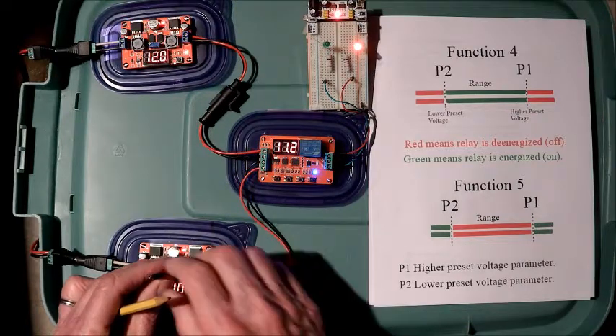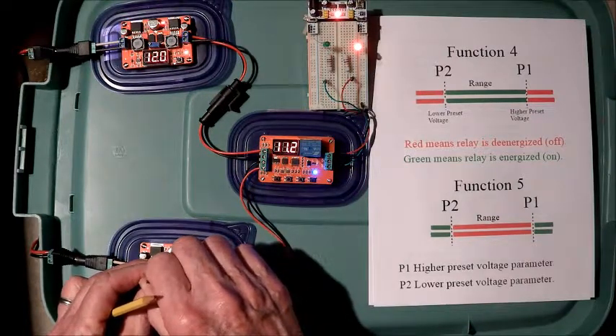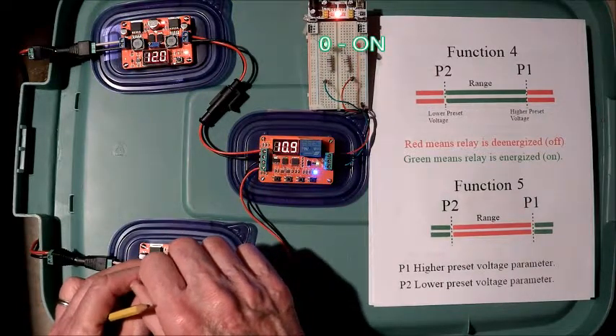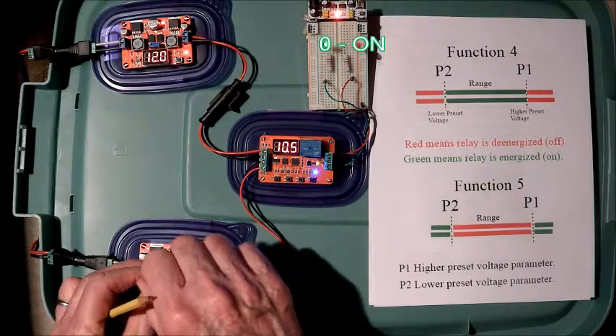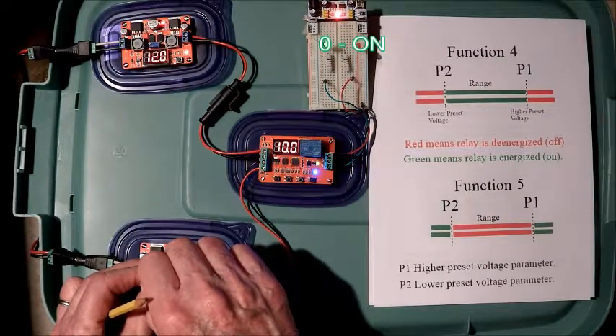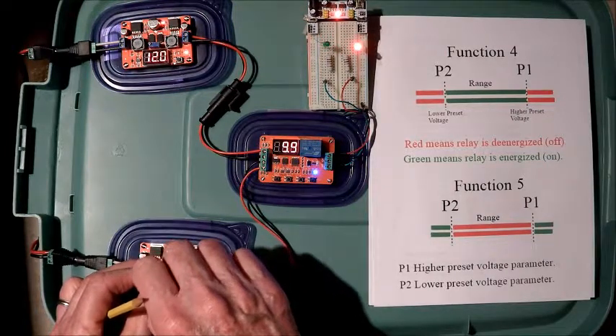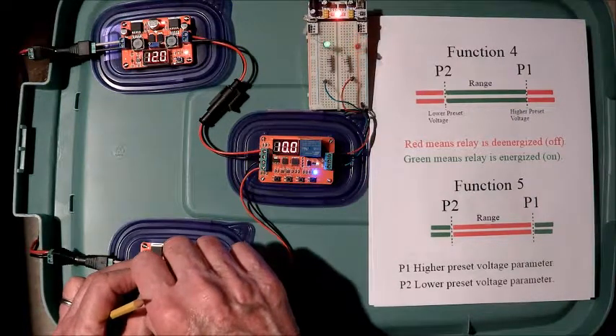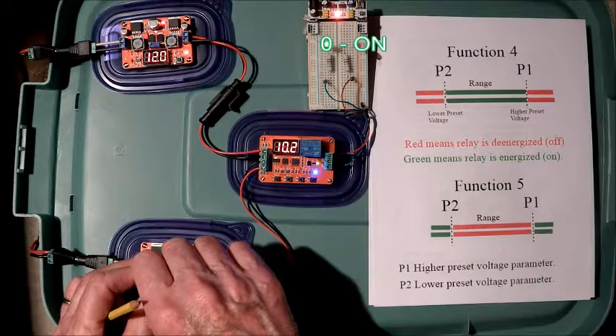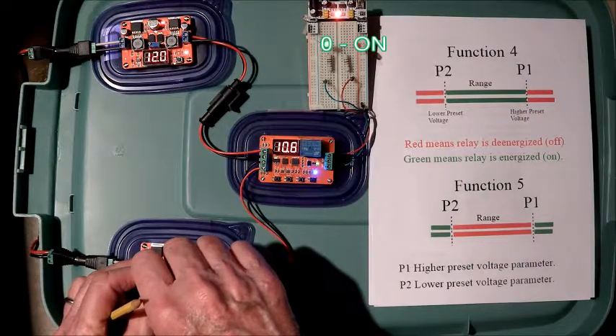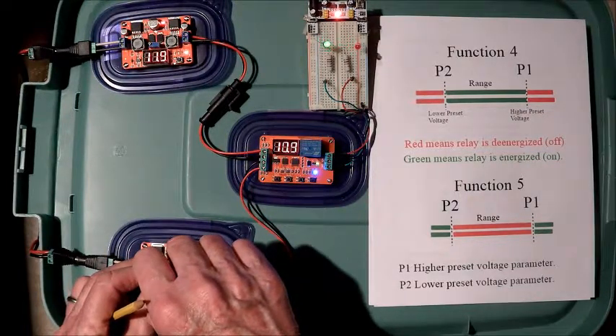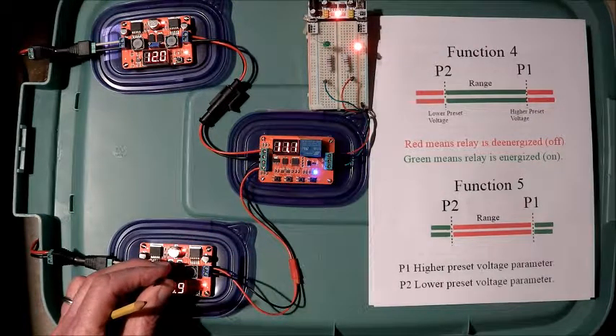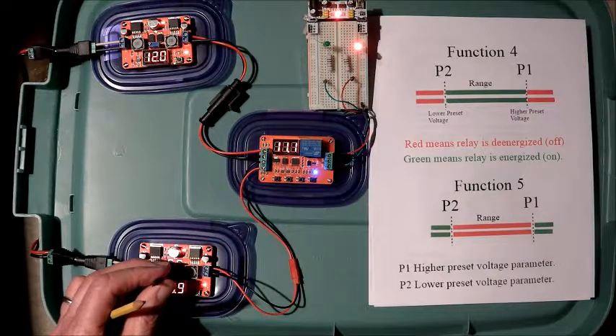Now, when we come down below the 11 volts, the relay should turn on. And there it is. Continue on down to the lower preset voltage, 10 volts. When we go on the other side of that, the relay de-energizes. We come up on the other side of that, over 10 volts, the relay will energize. And when we hit 11 volts, it'll de-energize. So, within range, the relay is energized. Out of range, it is de-energized.